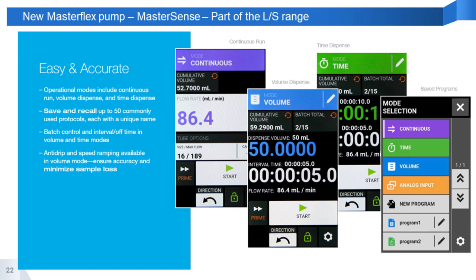Currently, operators need to introduce all the pump parameters manually based on the protocol we give them. So saving protocols in the pump itself could allow them to just click on the protocol on the touchscreen and run the program. So it would reduce really the times. And also, even more important, it could also eliminate the risk of setting up wrong parameters. So that's quite useful, yes. Perfect. So reducing potential human error. Yep, great. That sounds good.